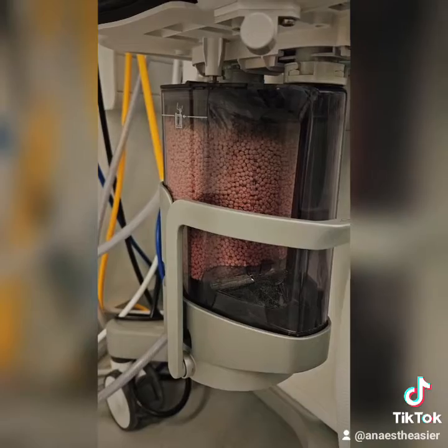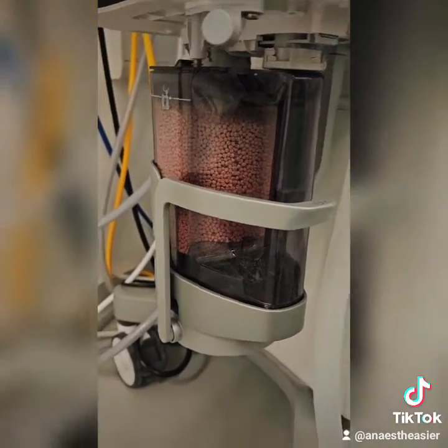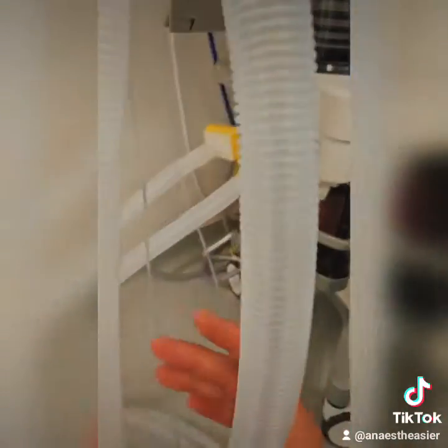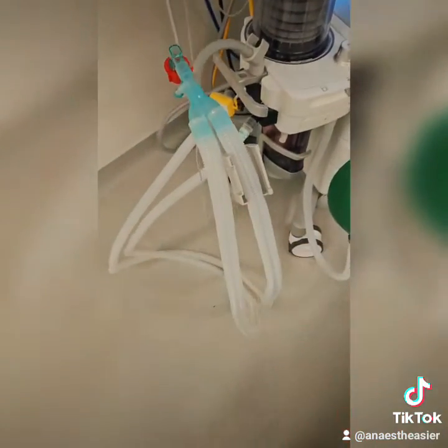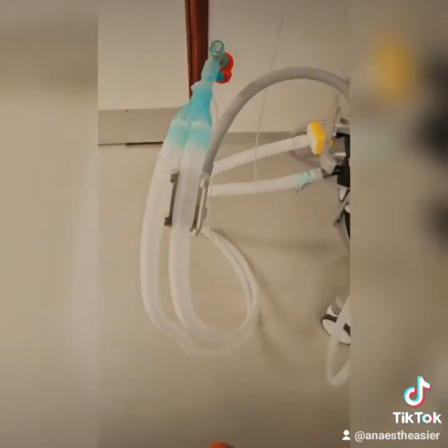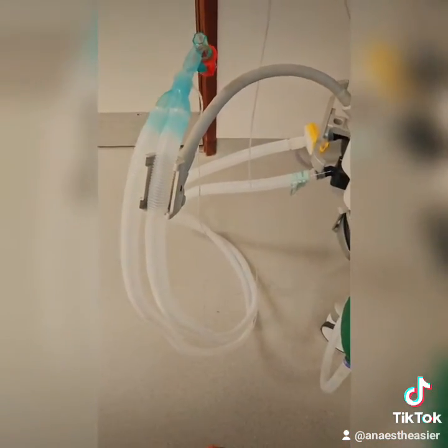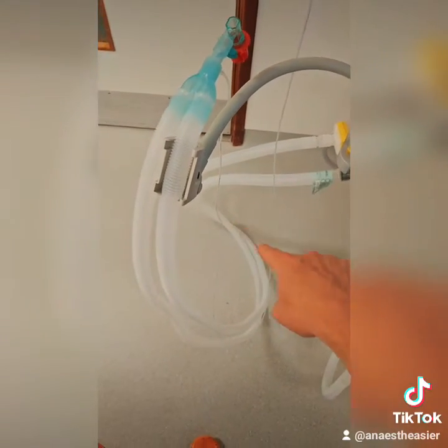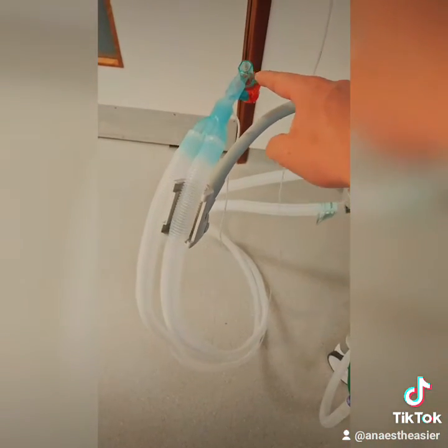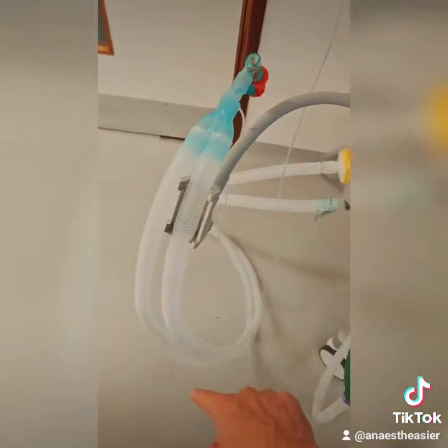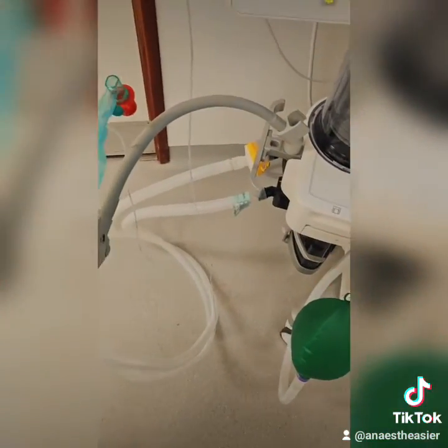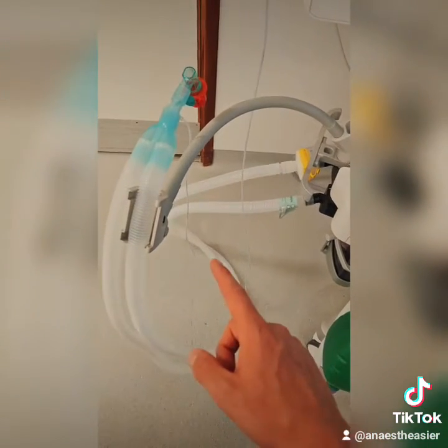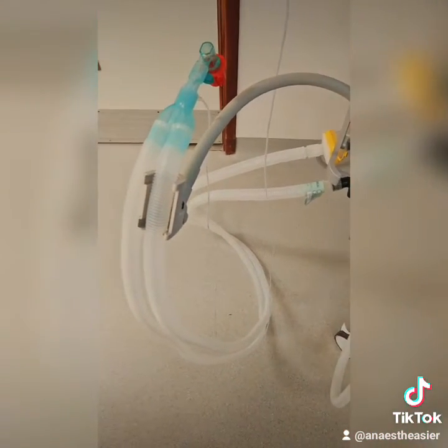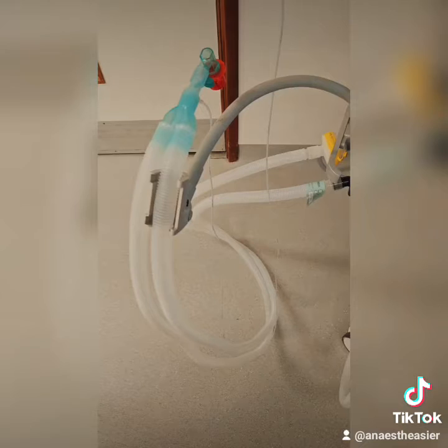This compound is very good at absorbing CO2. So we have a circle breathing system. So that's why this breathing circuit has two limbs. One is the inspiratory circuit and one is the expiratory circuit. The idea being the patient can inhale through one of these tubes and then breathe in, and then exhale, and it goes down the other one, and it goes back into the machine. And that means you can recycle oxygen and sevoflurane really efficiently, and you can put the flows really, really low, and you're not wasting lots of gas.